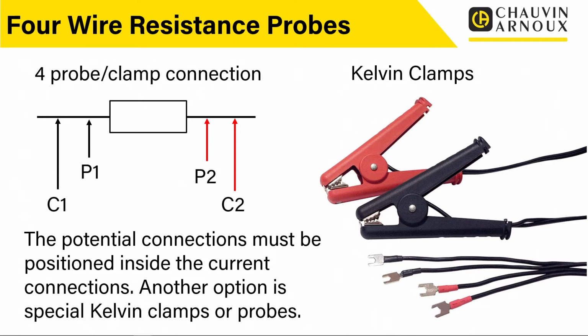So there are other options, and one we've got on the right hand side of the slide here is what we call Kelvin clamps. And these are quite clever crocodile clips, because you've got a different wire going to each jaw. One jaw will have the current connection and the other jaw will have the potential connection. So with 2 croc clips you actually have 4 connections. Because they're opposed to each other, when you clip them on, it doesn't really affect the measurement accuracy, because the connections are separated apart. So you've got both a potential and a current connection in each crocodile clip, and when you make those connections you're getting your 4 contacts, but only using 2 clips to do it. And it means it's quite easy to get to the actual contact points to take your measurement.